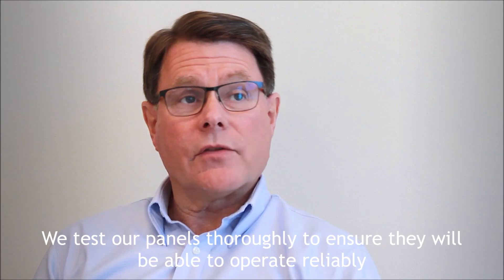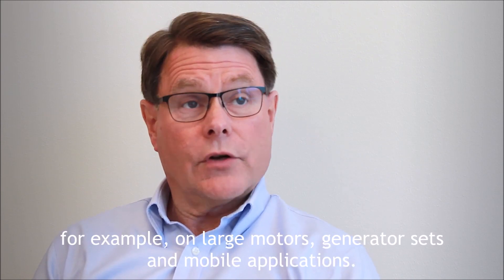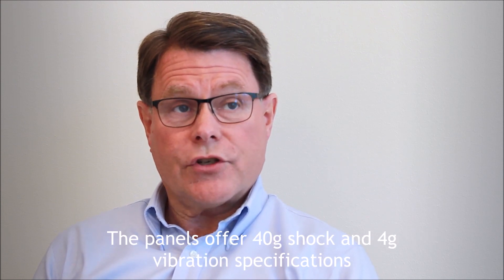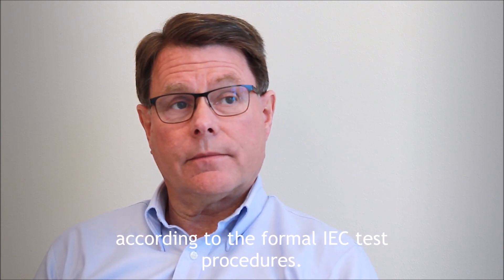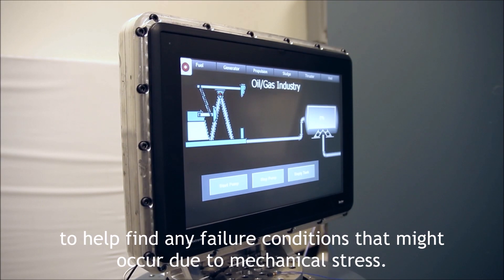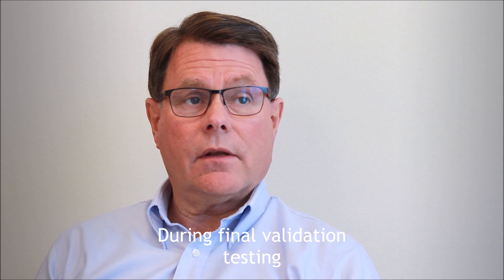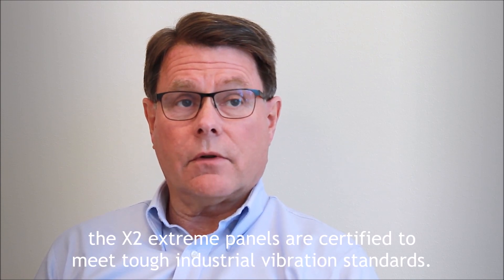We test our panels thoroughly to ensure they will be able to operate reliably in high vibration environments, for example on large motors, generator sets, and mobile applications. The panels offer 40G shock and 4G vibration specifications according to the formal IEC test procedures. This is tested on vibration equipment throughout the design phase to help find any failure conditions that might occur due to mechanical stress. During final validation testing, the X2 extreme panels are certified to meet tough industrial vibration standards.